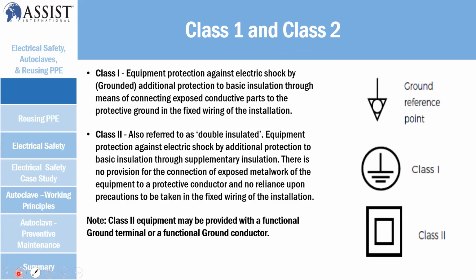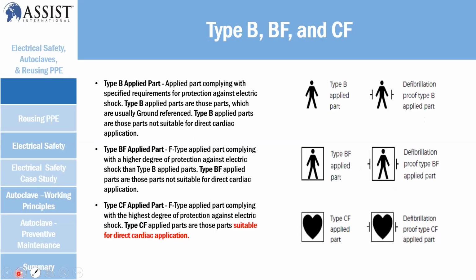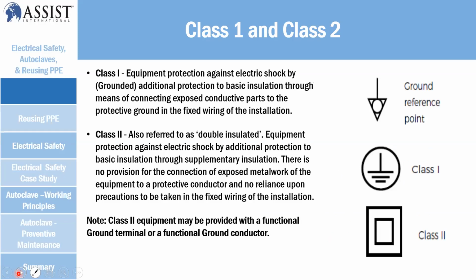For example, class one equipment is always referred to grounding. So you can see the ground reference point and class one symbols. You can see these symbols on the back of the medical device, or sometimes at the side of the medical device with the serial number. And a class two device is double insulated, so you're going to see this symbol on that equipment. Remember, for a class 2 device you normally don't need to do any ground testing because it doesn't have ground, but sometimes it has a ground connection that doesn't work. It depends on the manufacturer. So if you see a three-pin connector, you have to look into the user manual. Sometimes it will mention functional ground or not functional ground with the class 2 symbol.